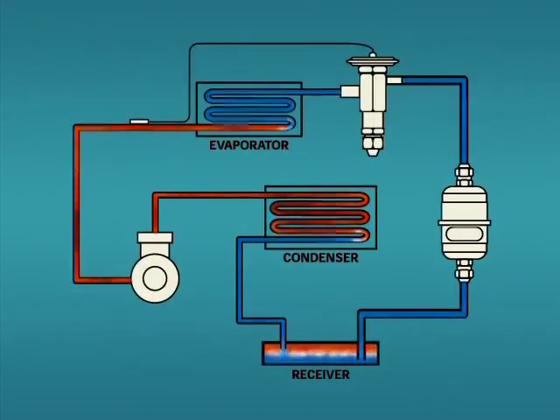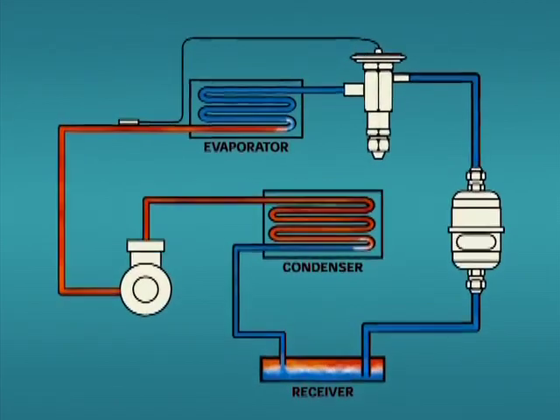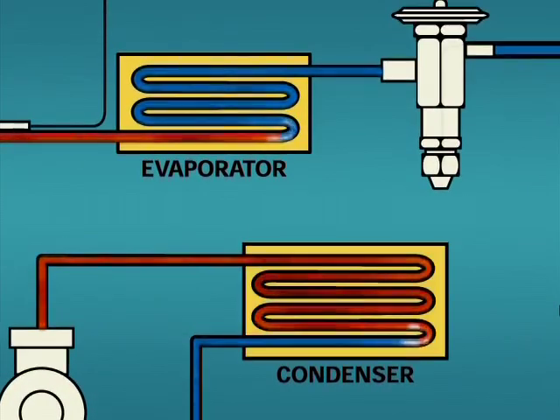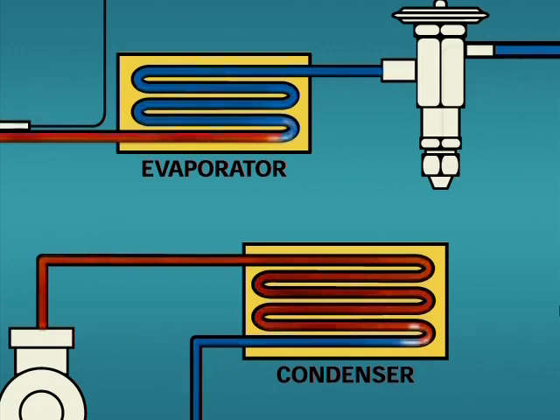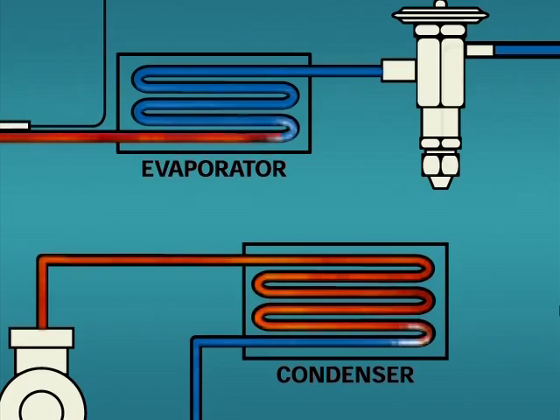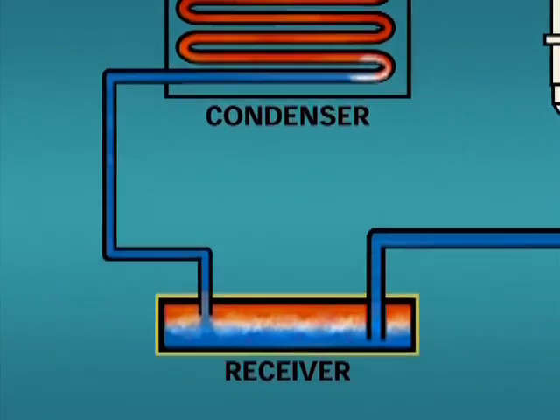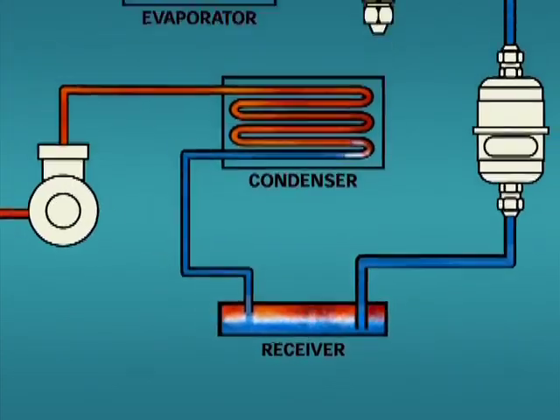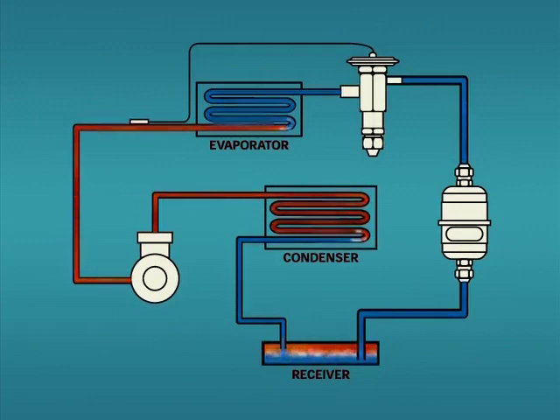Saturated refrigerant must exist in two places of a normal operating system: in the evaporator and in the condenser. This is due to the fact that the refrigerant becomes a liquid and vapor mixture in the evaporator and condenser. Anytime you have a liquid and vapor refrigerant mixture, the refrigerant will be at saturation.